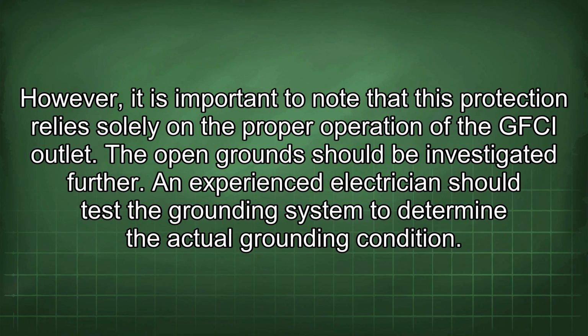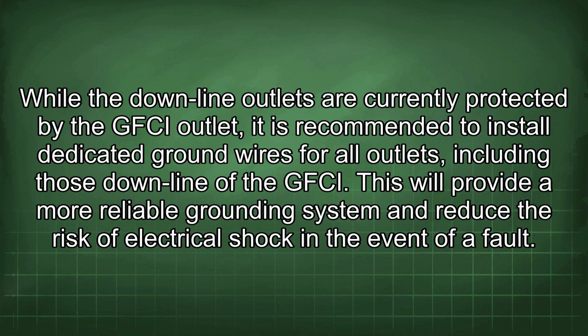An experienced electrician should test the grounding system to determine the actual grounding condition. While the downline outlets are currently protected by the GFCI outlet, it is recommended to install dedicated ground wires for all outlets, including those downline of the GFCI. This will provide a more reliable grounding system and reduce the risk of electrical shock in the event of a fault.